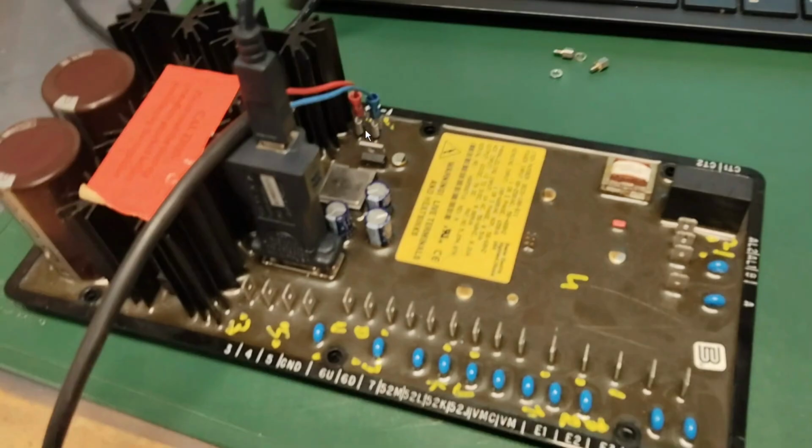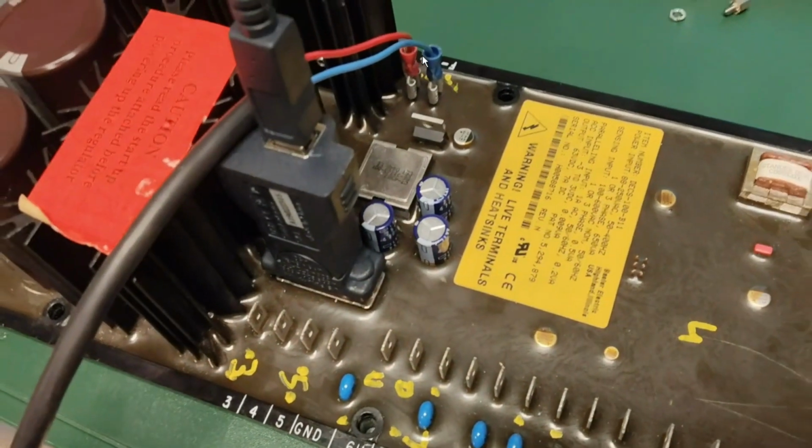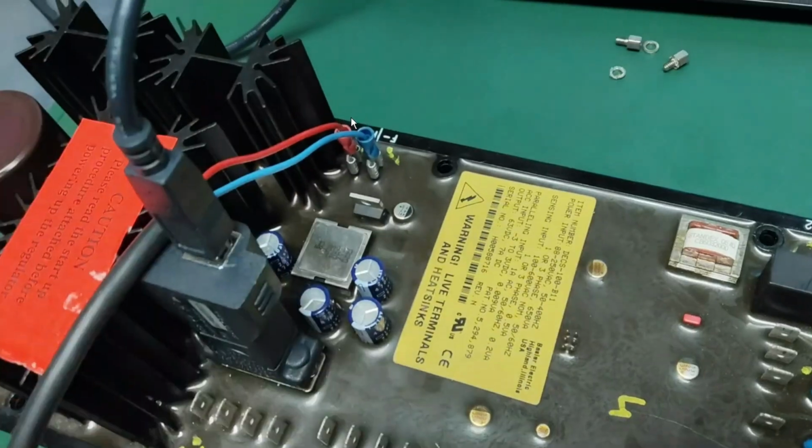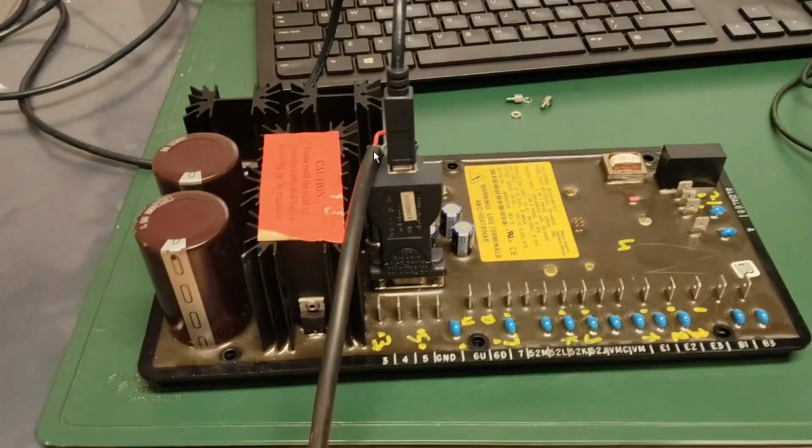You can apply DC and you can also apply AC, but if you want to apply AC, then you have to use more than 120 volt AC. In my case, I don't have a step down transformer, so I am using 24 volt DC only for the programming purpose. Don't use DC except for programming. For programming purpose, extracting, retrieving or uploading data, I am using 24 volt DC. I am using a converter from 220 volt to 24 volt, 5 ampere rating. You see how I connect. This DC is coming from this converter.